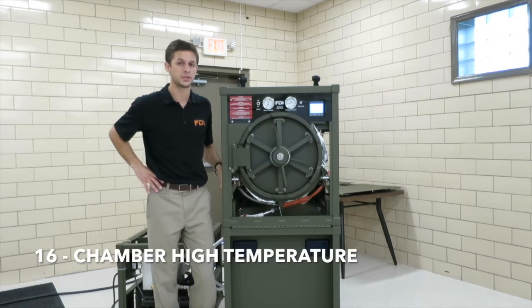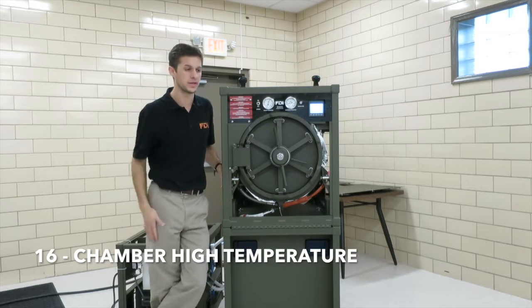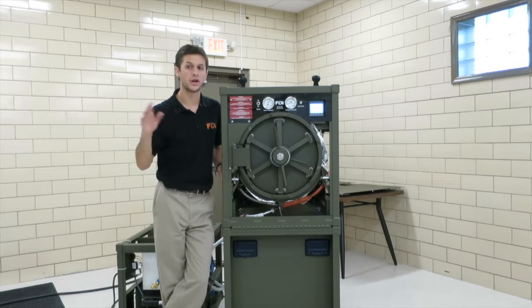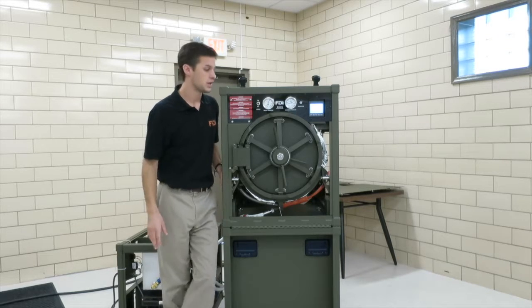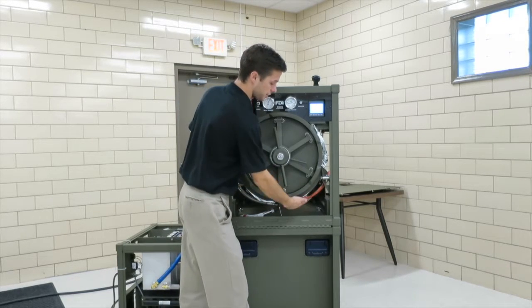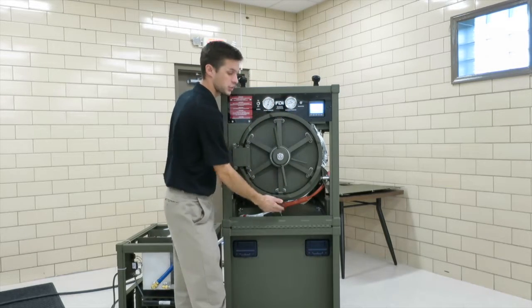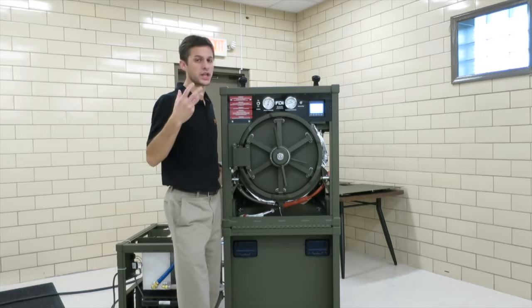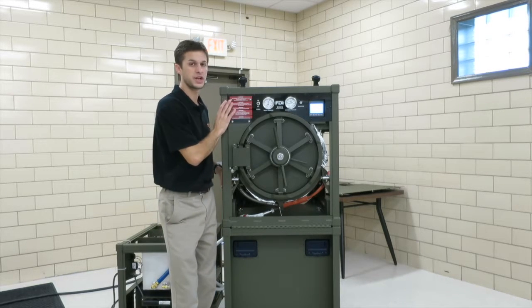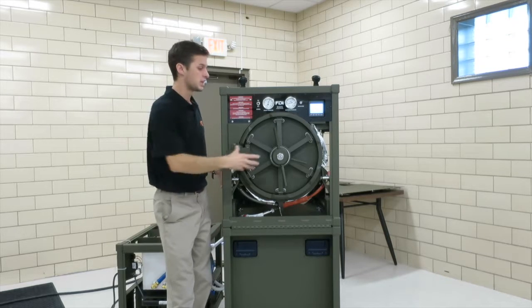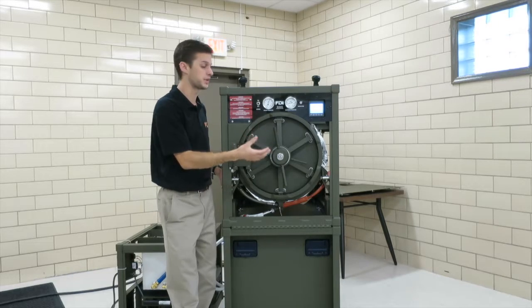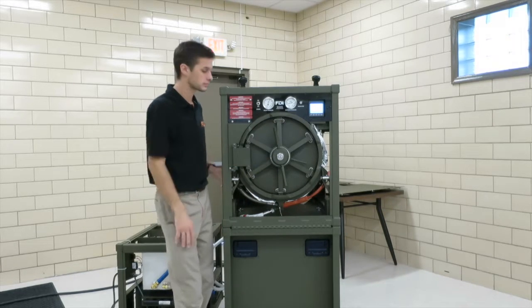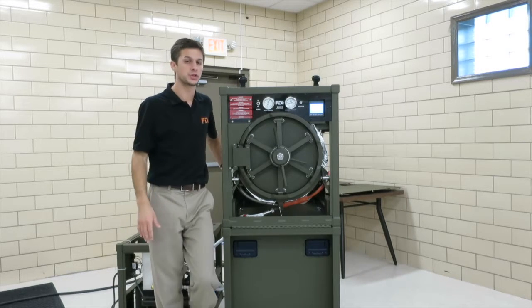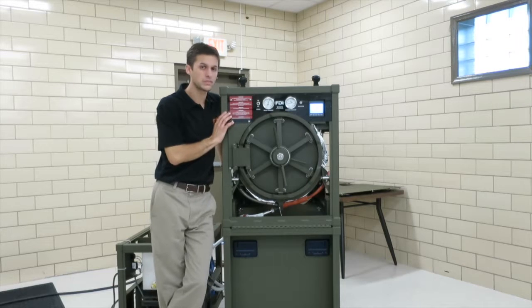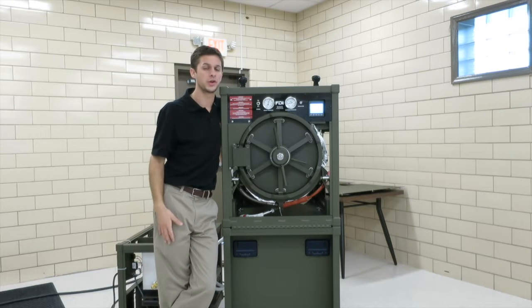Number 16 is chamber high temperature. This is just an upper safety limit. There's also another alarm that we'll talk about in a second, high exposure temperature. Both of these are coming off the temperature probe and the transmitters measuring the temperature in the chamber, but this is an upper limit. If during the operation of this sterilizer the temperature gets over a certain limit, just to protect, say, the instruments you're putting inside there, and to protect the system, you'll get this alarm. Typically you will get that high exposure temperature alarm before this, but if you're not in exposure, if you're in a different part of the cycle, you may get 16 chamber high temperature.